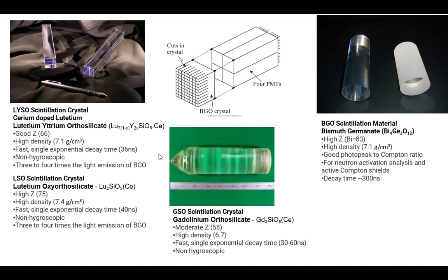So now you get to look at the crystals, right? This is something I want to add in because the book mentions some of this stuff, I believe, but they don't really go into any serious detail. So that's a fairly typical crystal. See how they've got the cuts in the crystal, right? So that's photomultipliers on the back of the crystal. You cut into the crystal because then you can put foil or anything between them. You can even just frost it, right? And what you'll end up with is light scattered between those little regions will be cut down drastically. They become like little flashlights pointing up.